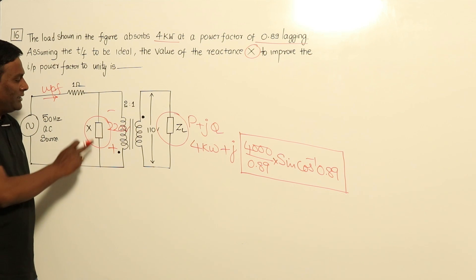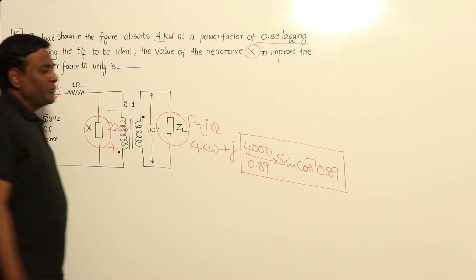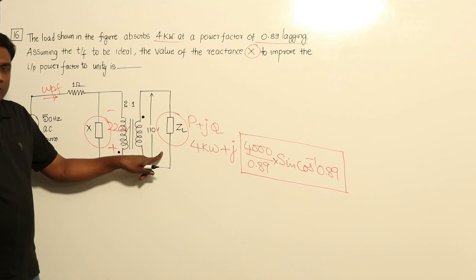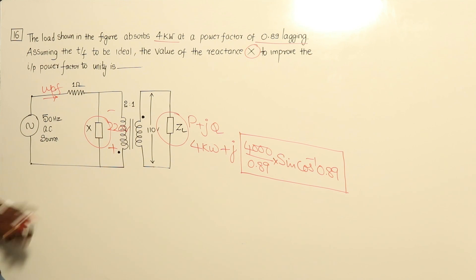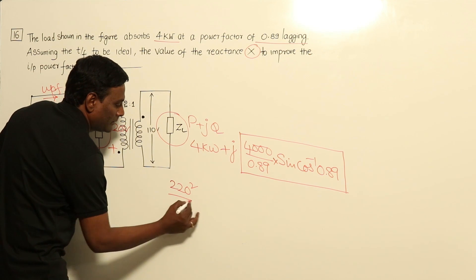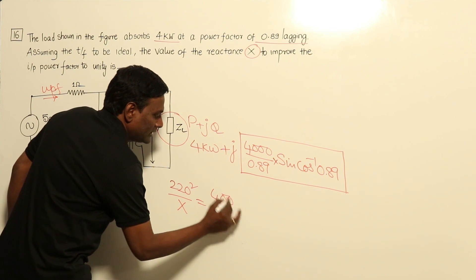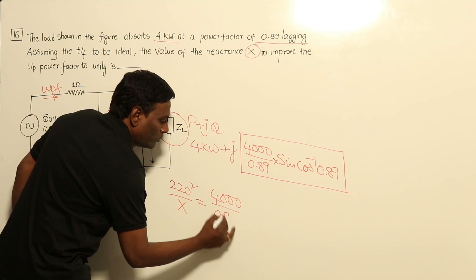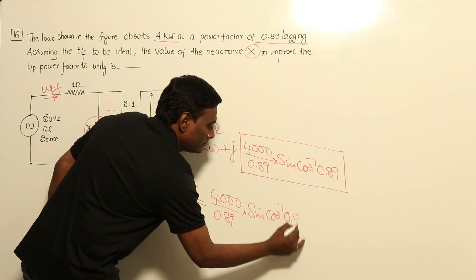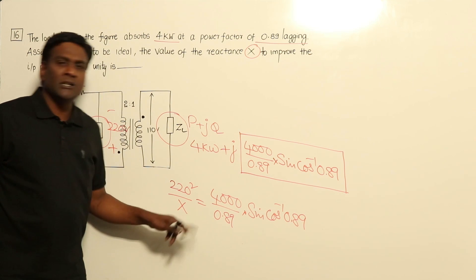For a resistor, the power absorbed is V²/R. Similarly, the reactive power is going to be V²/X. Now V²/X should equal the reactive power requirement of the load, so the source need not supply the reactive power. That means 220² / X equals the reactive power: 4000/0.89 × sin(cos⁻¹(0.89)). From this, X can be found — that is the Xc value.